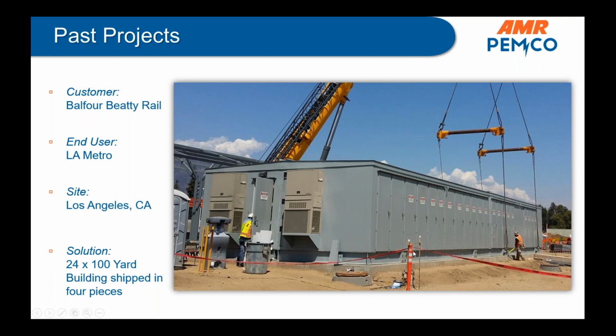Equipment access doors are down along the outside. For example, in California we put steel tubing all around surrounding these doors. So basically, this was a structural element without these doors in there. This whole wall can be removed if needed, for equipment access, to change equipment out 20 years down the road.